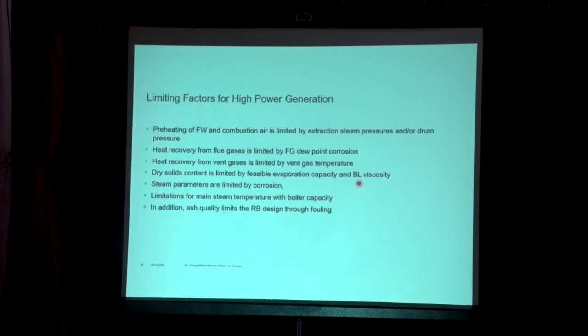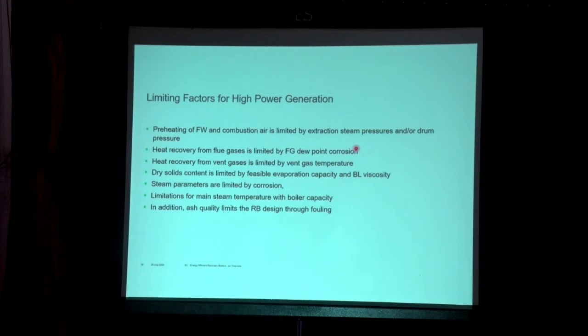The limiting factors for installation in existing boilers include: boiler capacity, feed water preheating and combustion air limited by extraction steam pressure or drum pressure, dry solid concentration limited by liquor viscosity and pumpability characteristics, and finally ash quality — specifically K and Cl content.